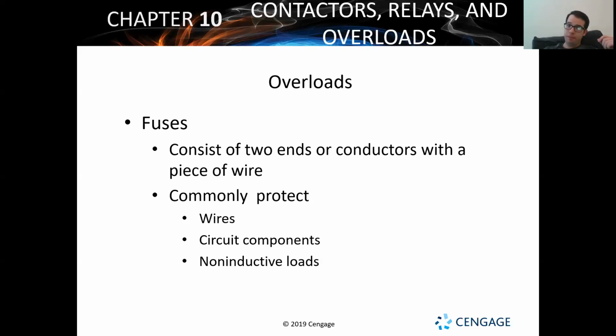Because we always know that a byproduct of electricity will always be heat. And that heat will be relative to the amount of amperage and voltage going through that and the amount of resistance present in the wire. Now, a fuse is typically very, very low resistance, almost zero, or as close as it can get to zero, because it wants power to pass through very, very easily. But if that power passes through so easily and yet it's still bringing in really high amperage and really high voltage, that's when the system will pop the fuse.